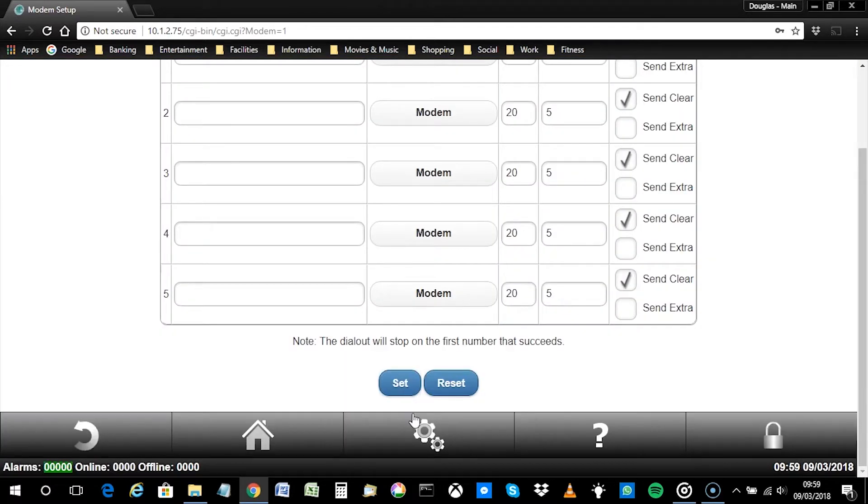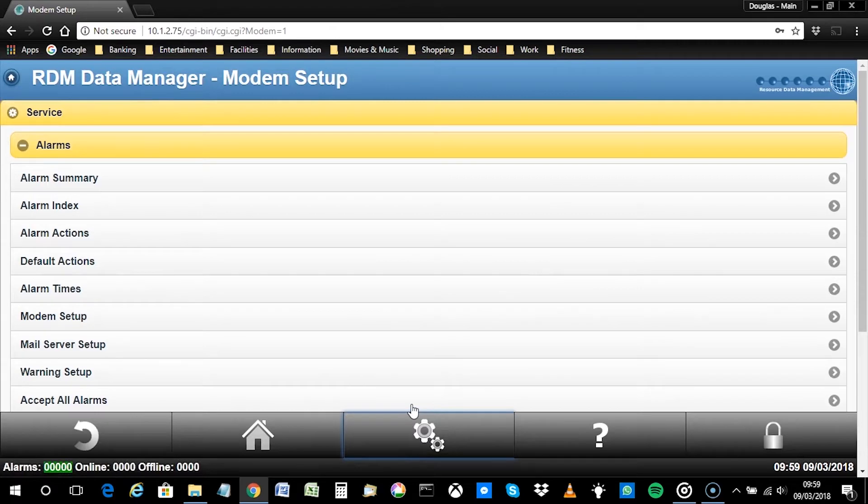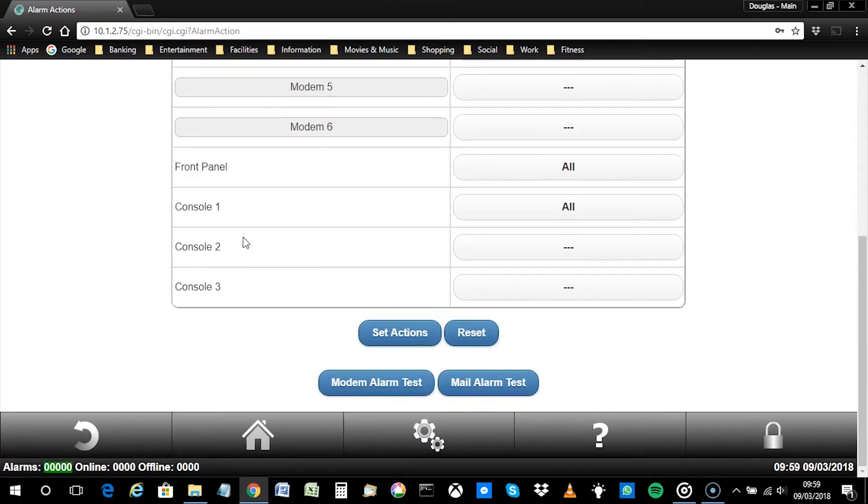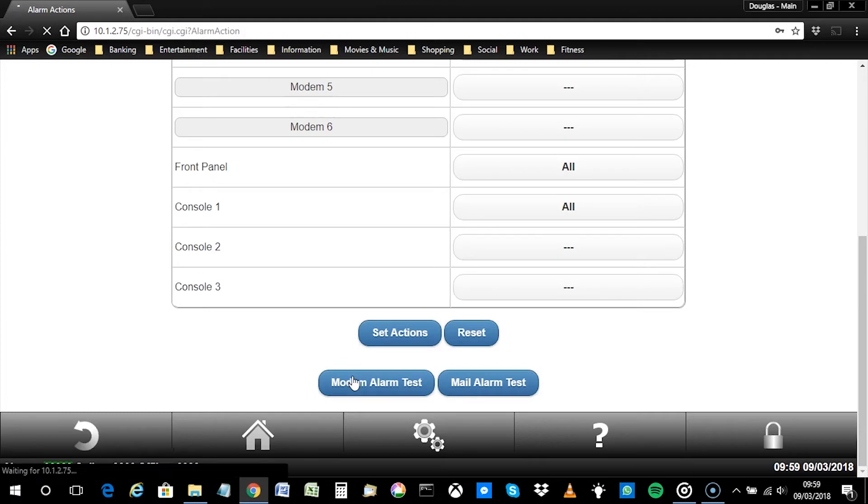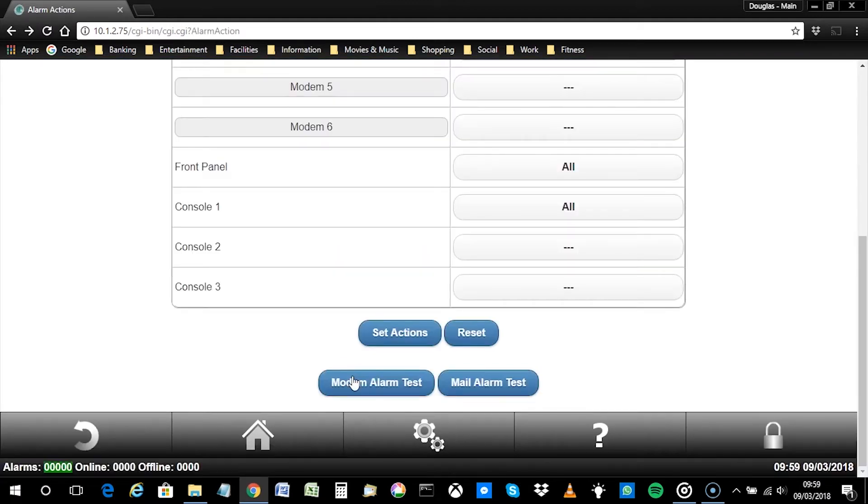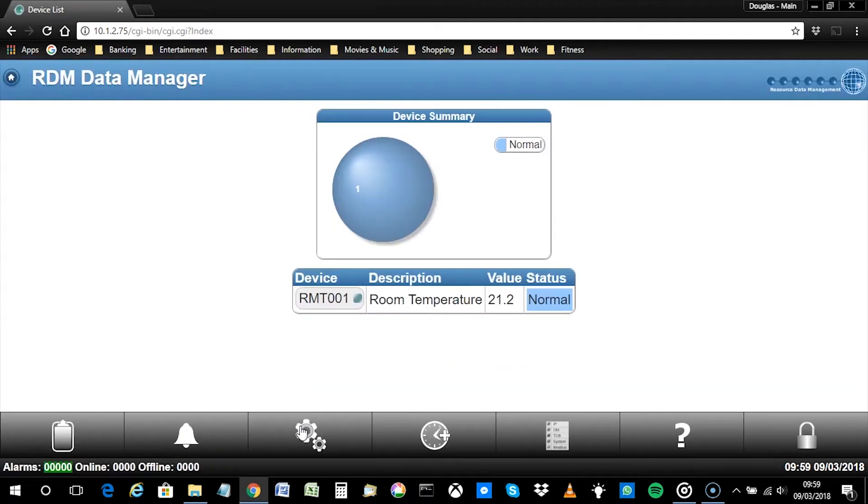Now click on the service icon before navigating to Alarms, then Alarm Actions. Click on Modem Alarm Test at the bottom of the page. This will generate a test alarm and send a test SMS to the configured recipient.